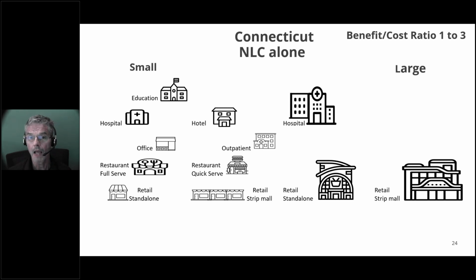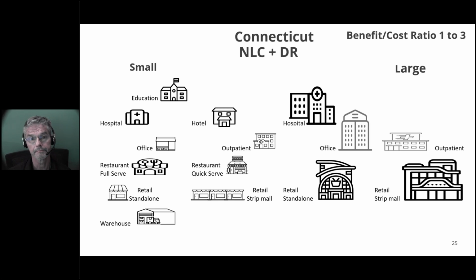In Connecticut, when installed along with a lighting upgrade but without demand response or HVAC integration, network lighting controls are cost-effective in most small buildings, plus large retail and hospital buildings that tend to have a high lighting power density with lots of bright lights. The benefit-cost ratio is in the range from 1 to 3.